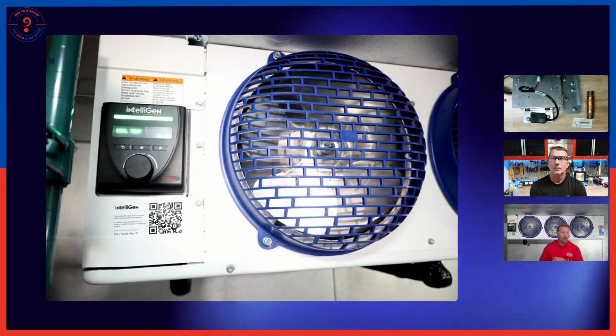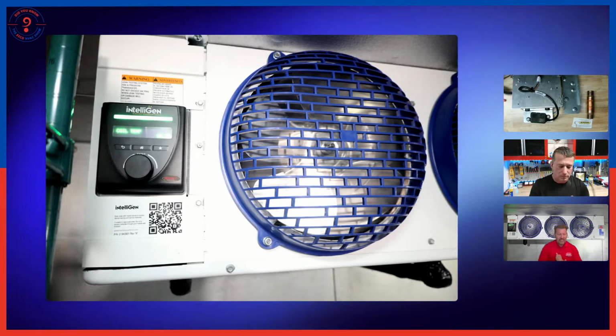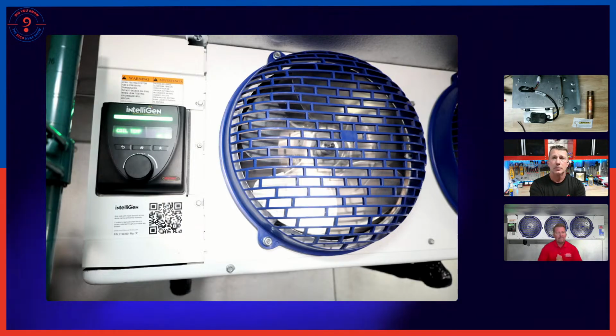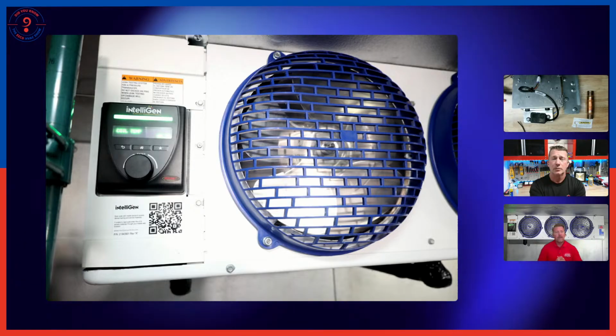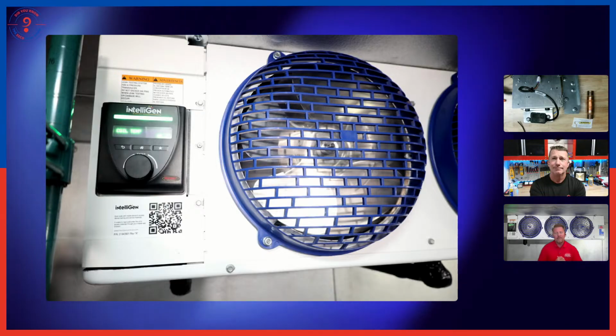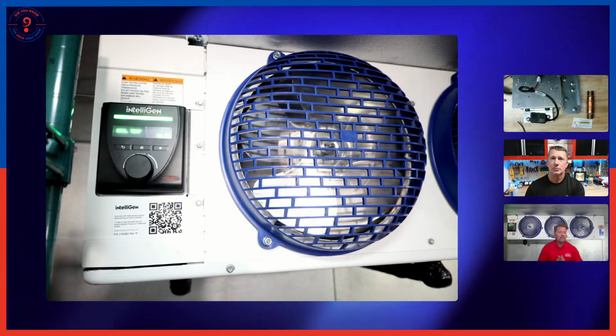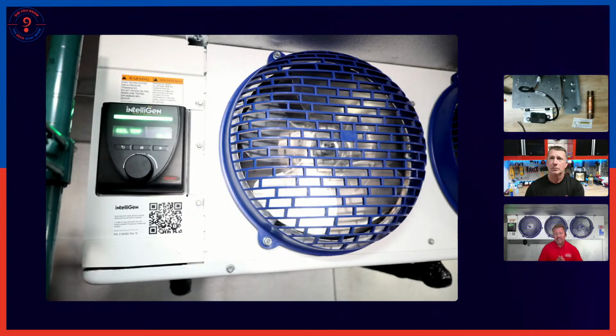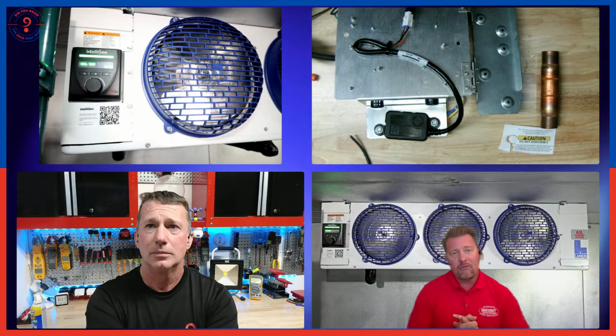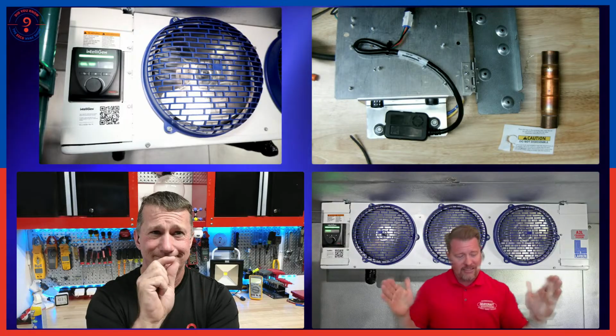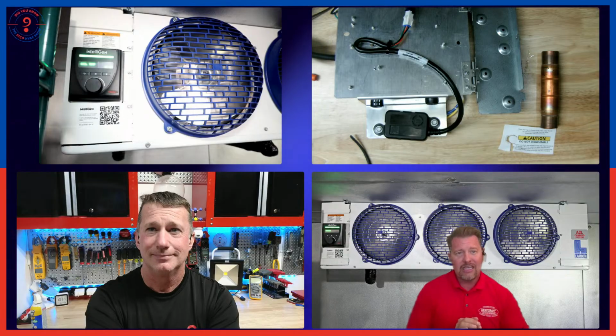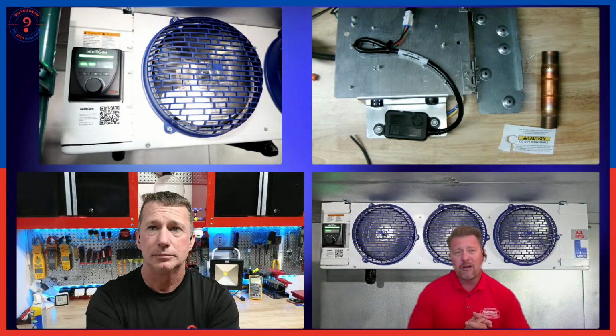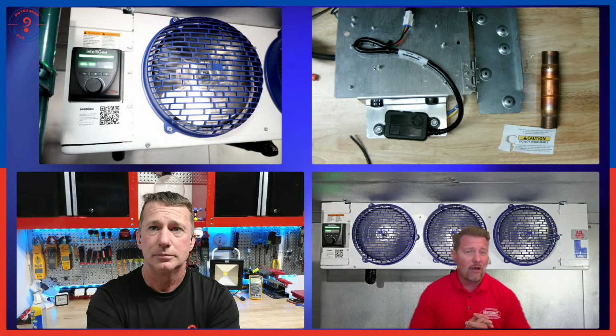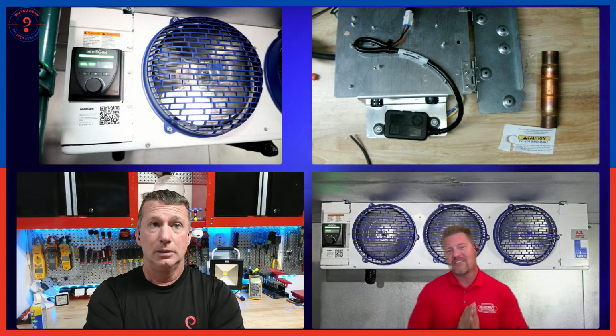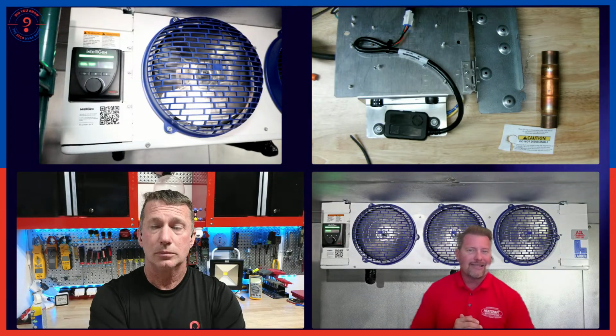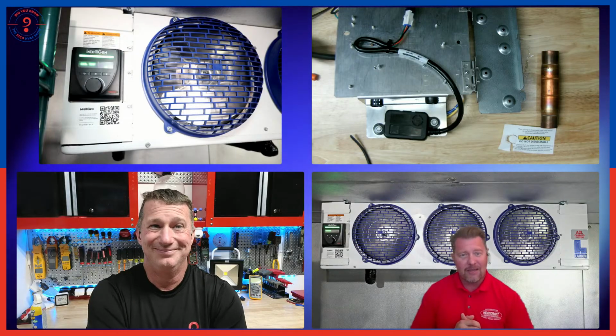So at this point, you would program this, initial programming. We programmed it for 448, set it for low temp electric defrost, set our temperature at -10. Once we click start system after doing those steps, that's all we had to do. It came on. We had a 4-minute time delay before it opened our expansion valve and went into our cooling cycle. At that point, no going back at the end of the day and setting a TXV superheat. Superheat's being controlled by the computer. And one great thing about EEVs, we can maintain superheat across a much wider spectrum because they have much greater capacity. The 201 valve that we use in this particular coil would be good from maybe 3,000 BTUs all the way up to about 48,000. Really? So one valve covers a vast array of application. Again, as a technician, you mean I don't have to carry 27 expansion valves on my truck?